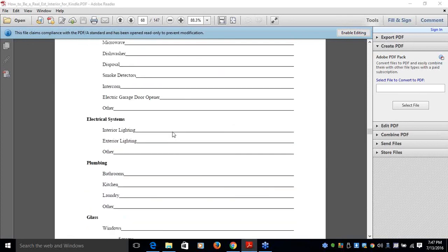Okay, electrical system. There's more to electrical than this. You have your electrical panel, you have your service line coming from the street, and you have your meter socket outside. All of those need to be in good repair. In fact, if the line outside is frayed, you generally won't pass an inspection, and you've got to replace that line. And when you replace that line, in most cases around North America now, they make you replace the meter socket at the same time. And also, if you replace the meter socket, guess what? You've got to replace the panel on the inside. So you could be looking at easily $1,500, $2,000 just to replace the panel, the service line, and the meter socket.